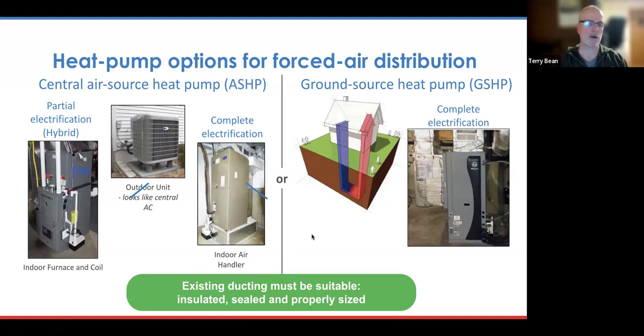But if the amount of air delivered in the space requires an airflow, that means that the air has to travel across the coil that conditions it too quickly, then the coil really doesn't get a chance to get the air up to temperature for heating or chilled sufficiently. So it's this balance with ductwork between the speed of airflow over that coil that's conditioning it and the amount that is needed to be delivered to deliver the BTUs needed for that space.